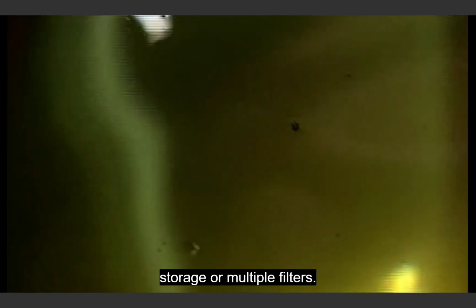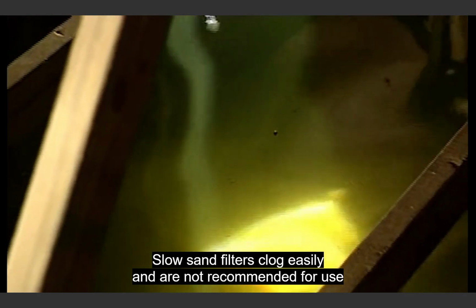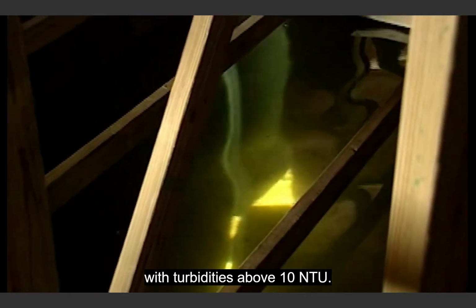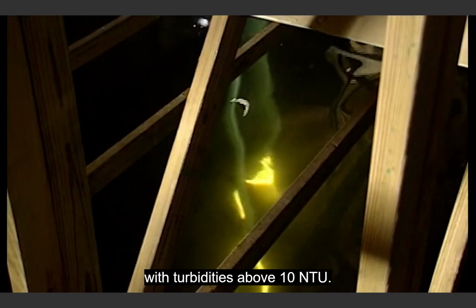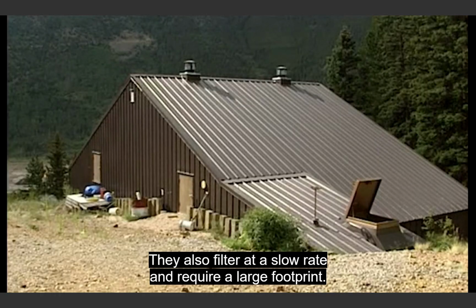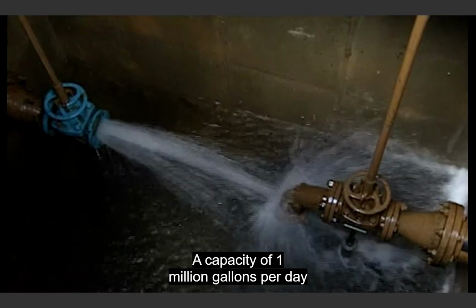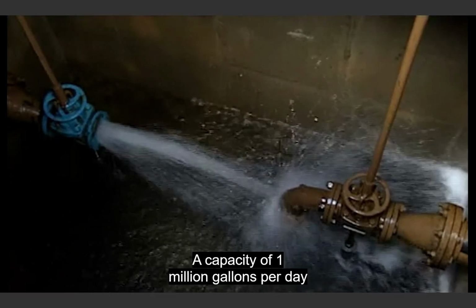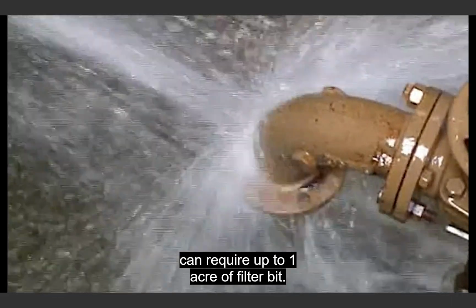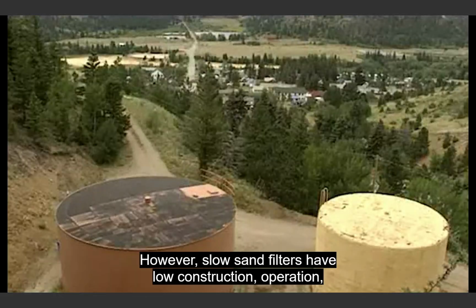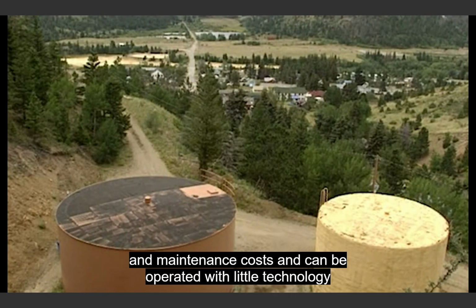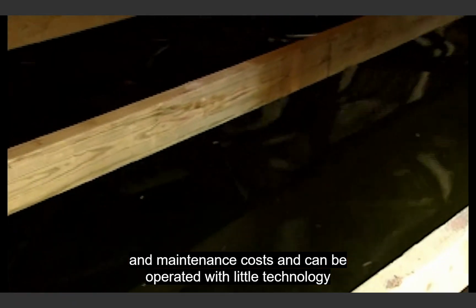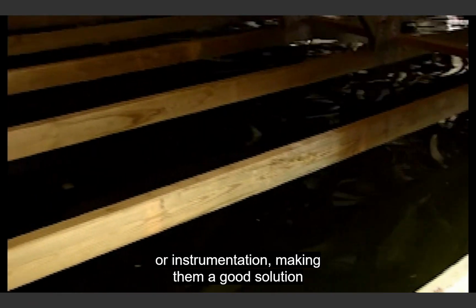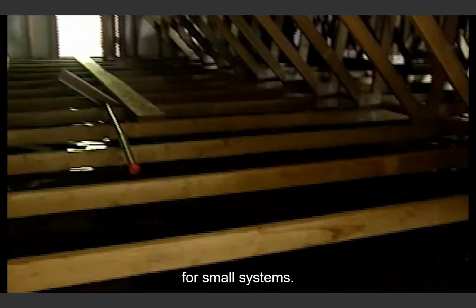Slow sand filters clog easily and are not recommended for use with turbidities above 10 NTU. They also filter at a slow rate and require a large footprint. A capacity of 1 million gallons per day can require up to 1 acre of filter bed. However, slow sand filters have low construction, operation, and maintenance costs and can be operated with little technology or instrumentation, making them a good solution for small systems.